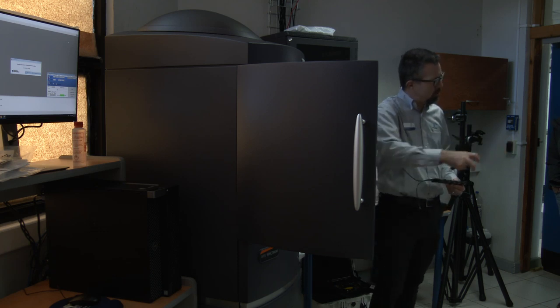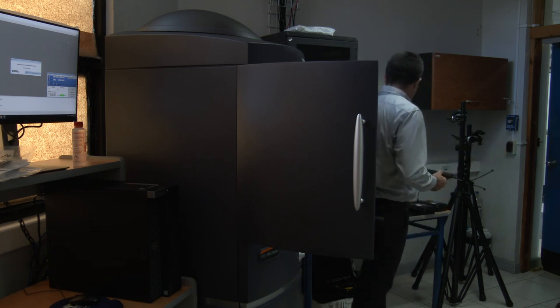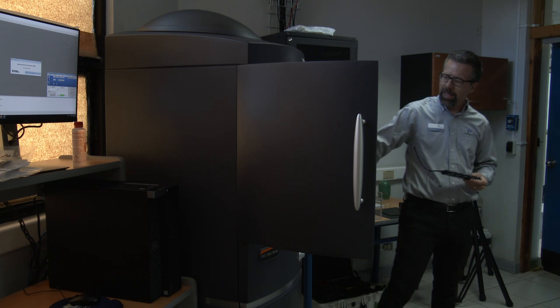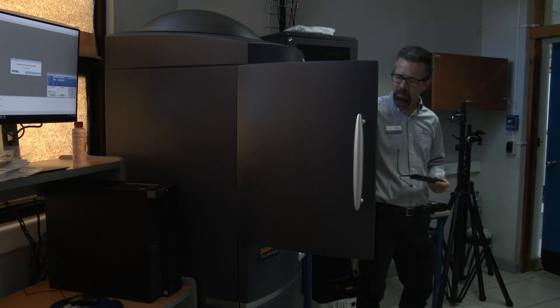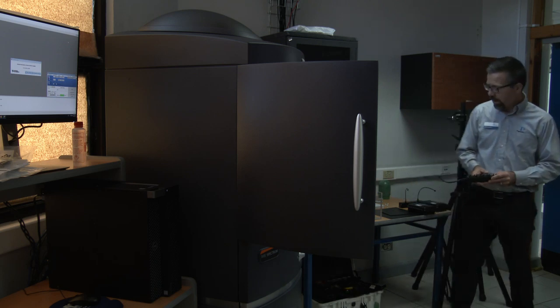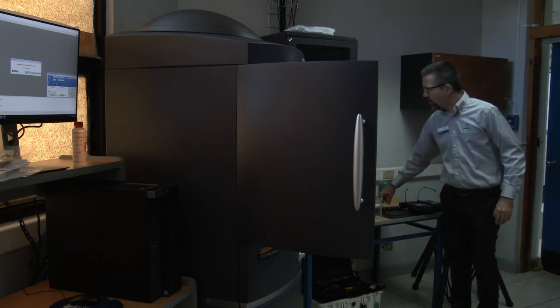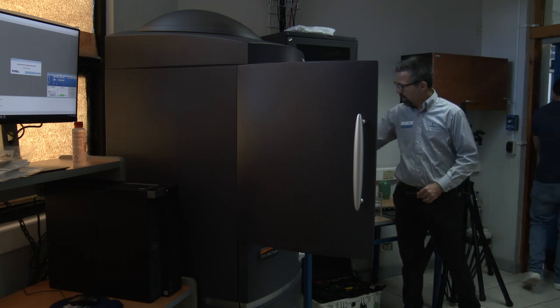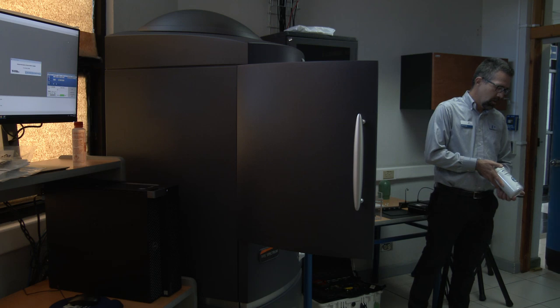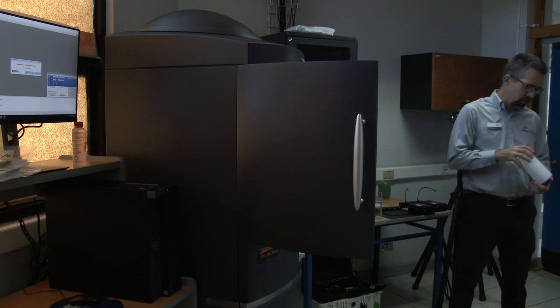There's a pipe that has some perforations in it, and I just have this set to a very minimal amount, just a little bit less than atmosphere, so that in case any isoflurane were to be in here, it would roll off, go down to the bottom, and then be educted out. When it's vacuumed out, it's then sent to this. This is a charcoal canister. So this is refillable carbon.